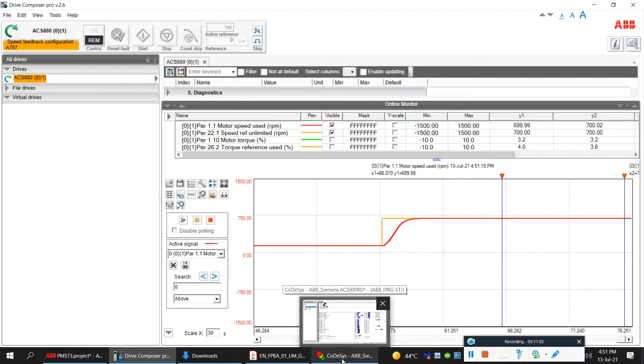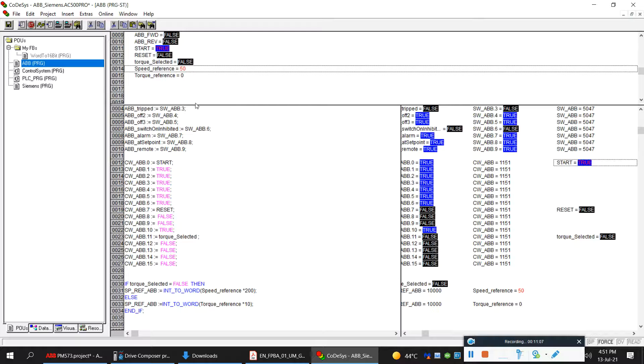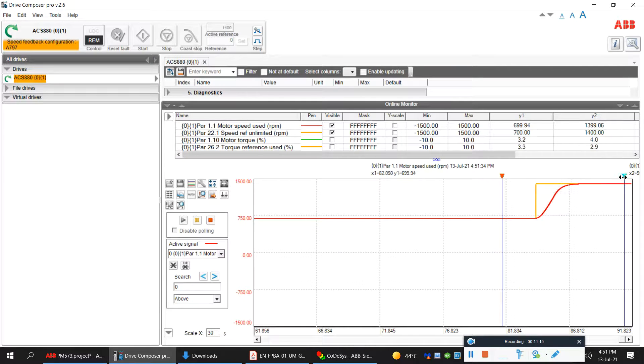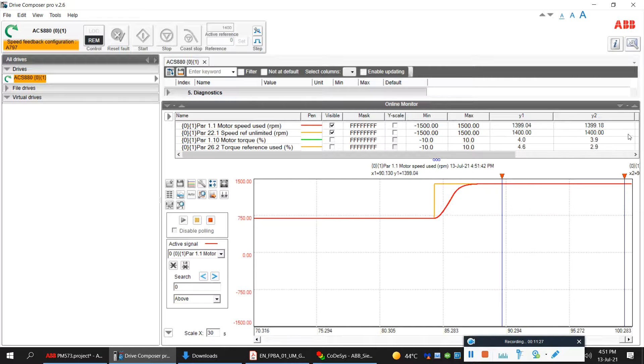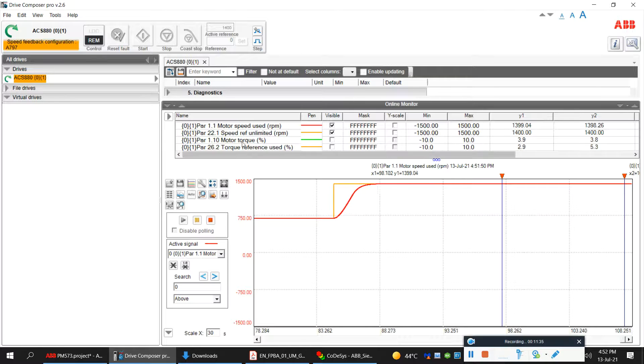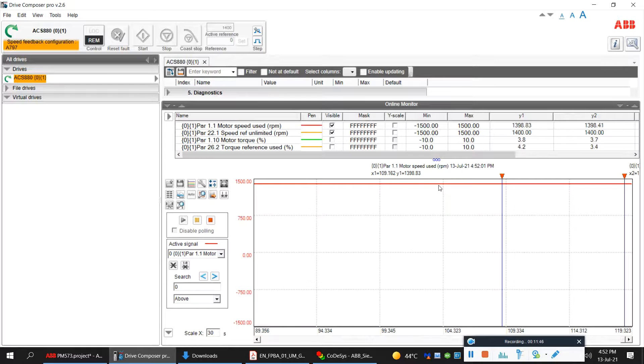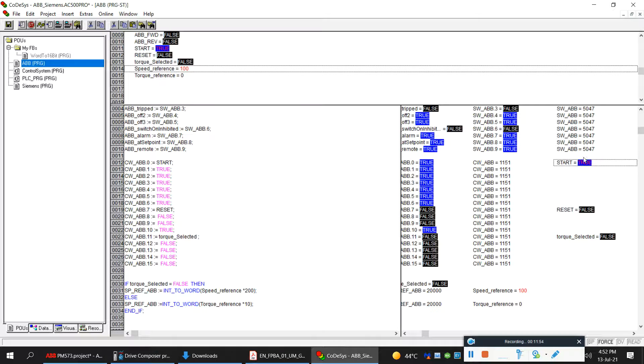Let's run at full speed. You can see the motor torque is almost four percent — meaning to run the motor at full RPM it takes around four percent torque. This basically explains speed control: I directly give the speed reference, the drive follows that reference, and whatever torque is required the drive's target is to achieve that speed reference. That covers speed control — now let's stop and move to torque control.